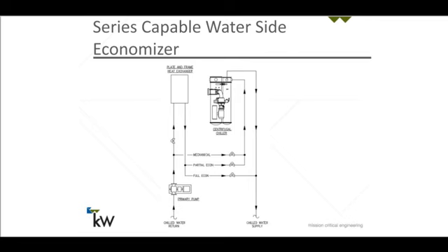You've got your water coming back from your data center, chilled water return. It's passing through a pump, and when you can use the cold condenser water to create chilled water, you open the valve to the heat exchanger. That water comes out of the heat exchanger.